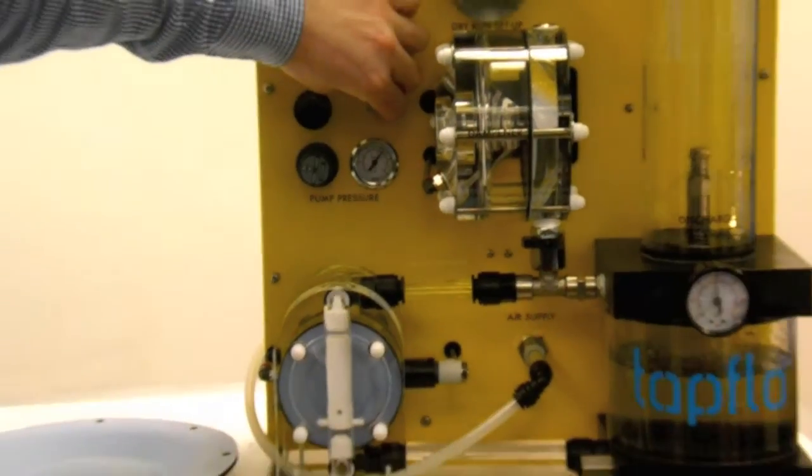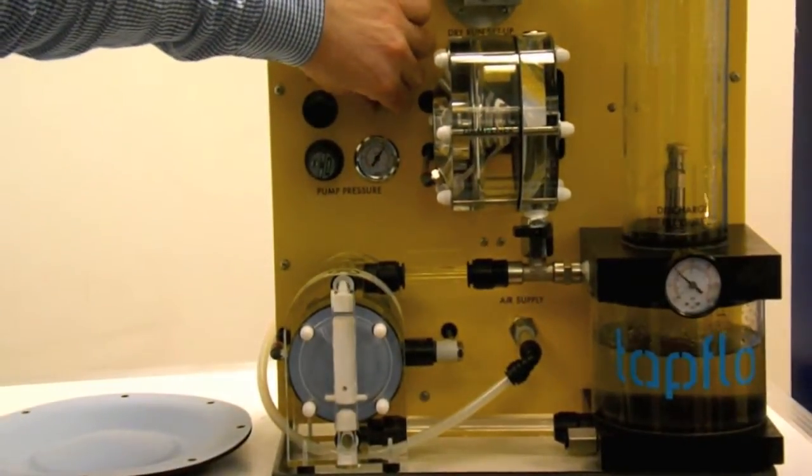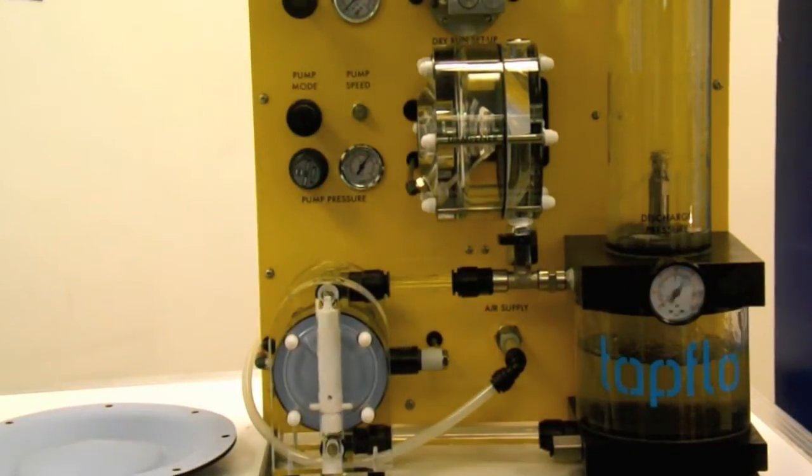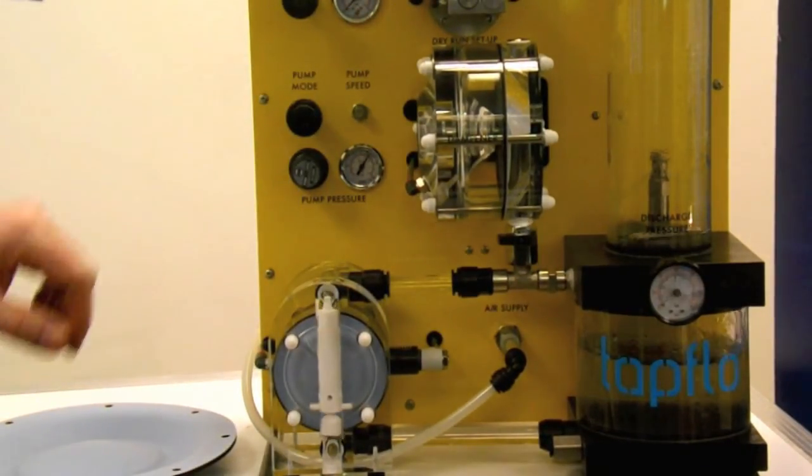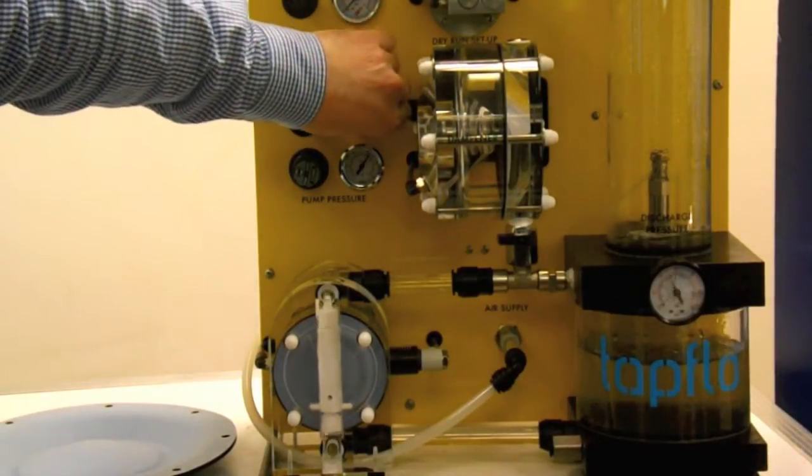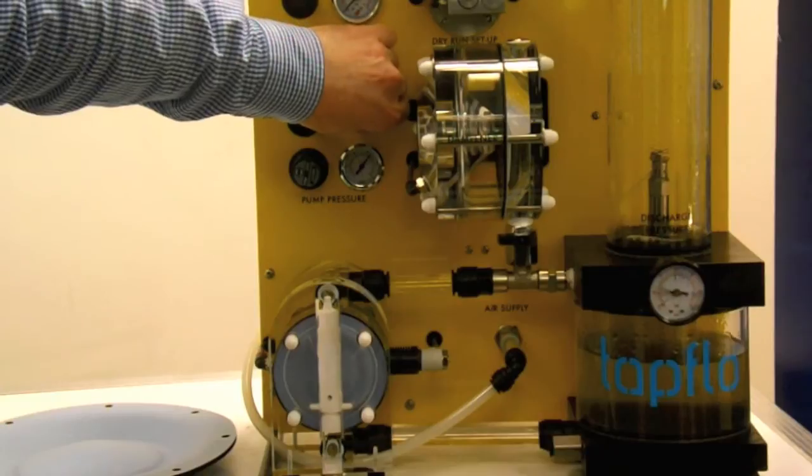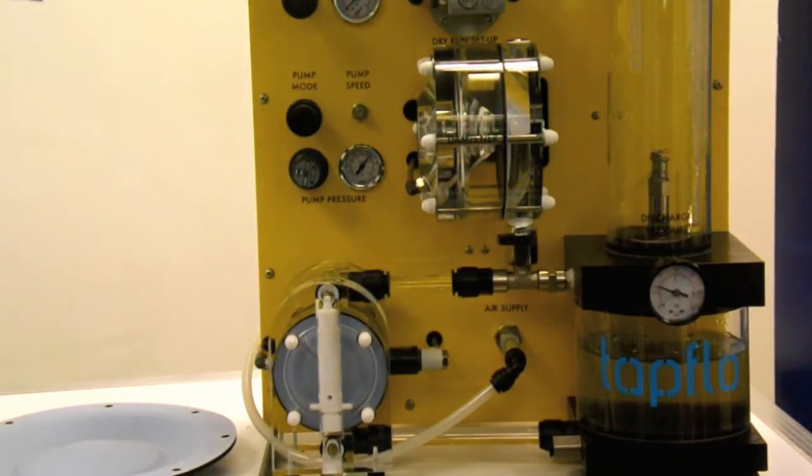You can see here we have the pressure for the pump set just around 5 bar and the pump is running nice and slowly. By opening up the needle valve we can increase the speed and intensity of the pump and by closing the needle valve again we can slow the pump down and have a nice slow speed if we need it.